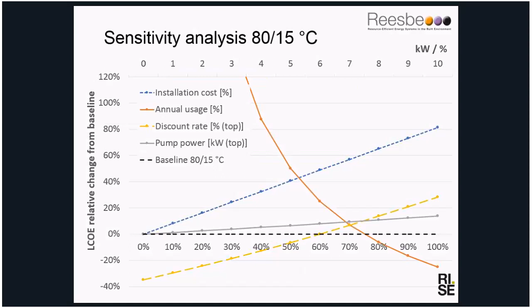The biggest constraint for this technology is the temperature of the thermal grids, or district heating. And the majority of district heating, of course, in Europe is 3rd generation, so generally below 100 degrees Celsius. With this particular technology, most low temperature organic Rankine cycle modules are optimized for 120 degrees. But those innovative vendors that we were considering are optimized for 90.